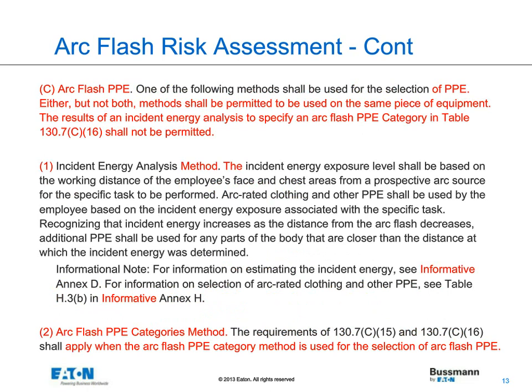Moving on to Part C of the arc flash hazard risk assessment, we have two choices when it comes to selecting PPE, and the change here in the parent text of C indicates that you have to do one or the other, but you cannot use both. So they don't want you to mingle between using the analysis method and then try to convert over to the table. So it would never be appropriate, for instance, to calculate the incident energy and then use the tables to dress for that hazard. Again, you have some guidance, and it shows you that there is an Annex D.